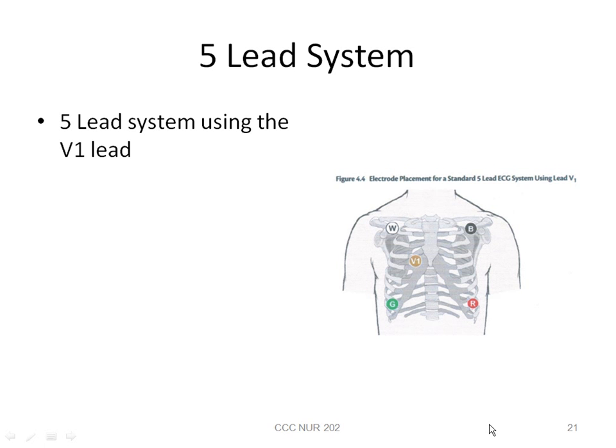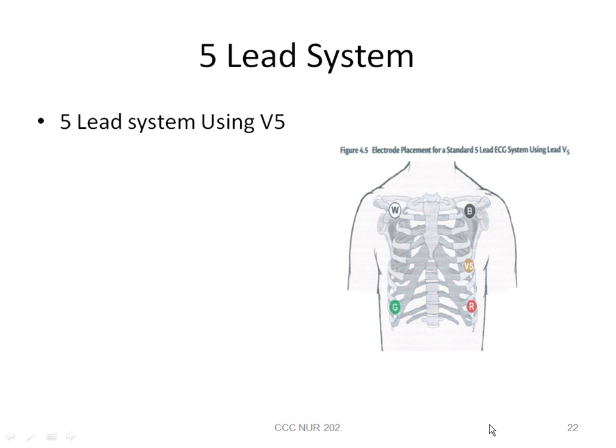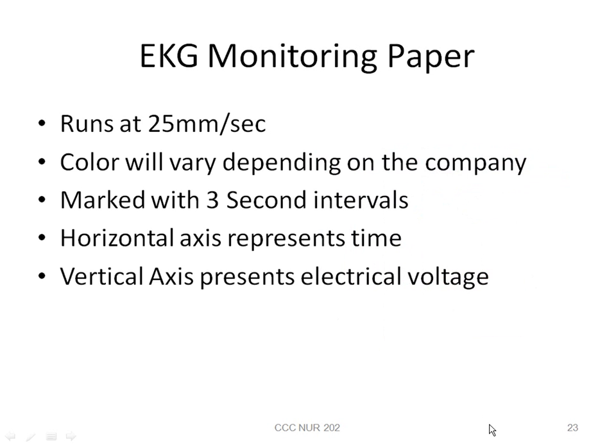But this is particular. You know, clouds over grass, smoke over fire. One way to remember, white over green, clouds over grass, okay? Or smoke over fire, black over red is one way. I saw one book, snow on tree, okay, for the white over green. Whatever acronyms or however you want to do it, to remember it is fine, as long as you kind of get a good idea of where they need to go. Again, just another 5-lead system.